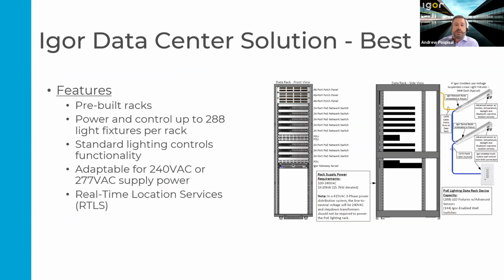So again, these are pre-built racks similar to the better solution, designed to really be rolled into place, connect your power, and then as far as field terminations, this solution would have the patch panels and simple, typical Cat6 punch down on the back of those panels, and then those cables will go out to the fixtures or out each pair of fixtures. And as I mentioned, support up to 288 fixtures per rack. All the standard lighting controls I mentioned before. Again, similar compatibility on power supply voltage, 240 or 277.